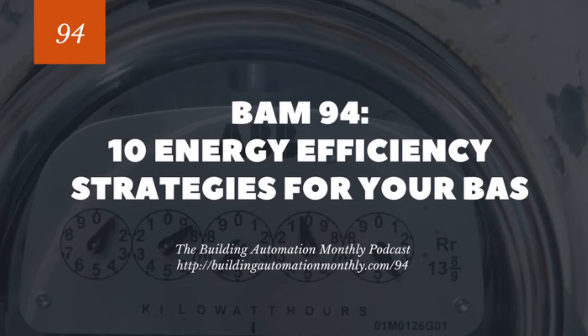Now, you can continue to do that until you hit a point at which the conditions of the environment deteriorate. Usually that's about at the 30-minute mark. Most spaces are 4 to 6 air changes, meaning that the volume of air will change within the space every 15 to 10 minutes. And what that means for you is that you're going to have maybe 2 air changes that you can do before the air gets hot enough that folks are like, it's getting uncomfortable.